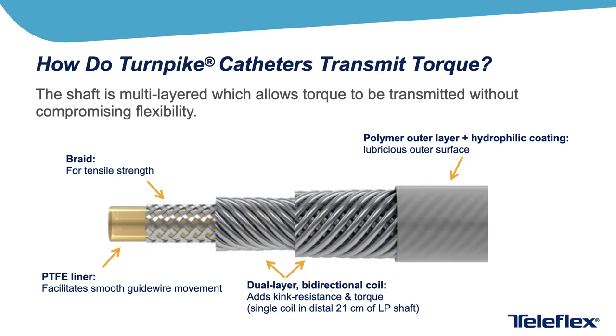The braid's function in a microcatheter like the Corsair or the Turnpike is to protect that guidewire lumen, so as you're torquing it, the coil isn't allowed to turn down and impede the guidewire lumen when twisting in the direction that causes it to contract. Conversely, when torquing in the opposite direction, the polymer is there to bound the outward movement of the coil as well, so you get torque transmission when the coil is bounded.